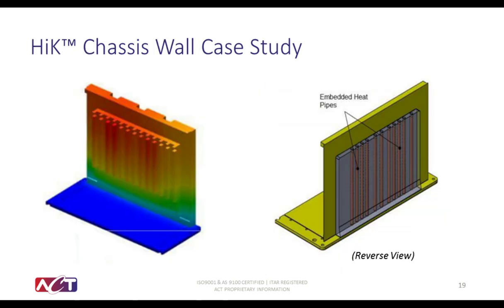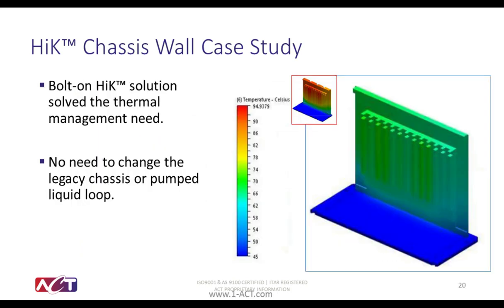Another brief case study is taking a chassis wall, which is liquid cooled on the bottom, and applying to it an embedded heat pipe plate to spread heat from that chassis wall and the cards down into that liquid rail. As you can see on the left side of this image, when that plate had no heat pipes and was only a conduction-based solution, it had these hot spots occurring near the top of the card. By adding an embedded heat pipe solution to the reverse side of that card, ACT was able to decrease the temperatures seen across that card by 20 to 30 degrees with no change to the legacy chassis or pumped liquid loop.